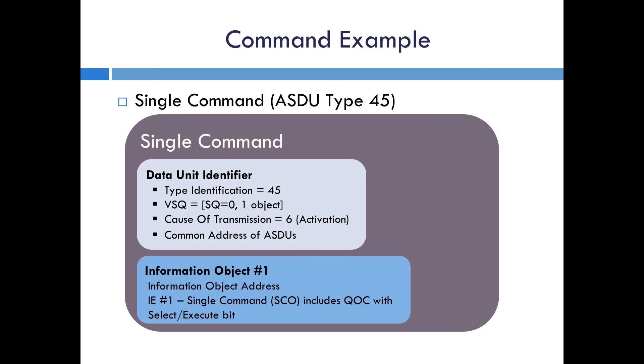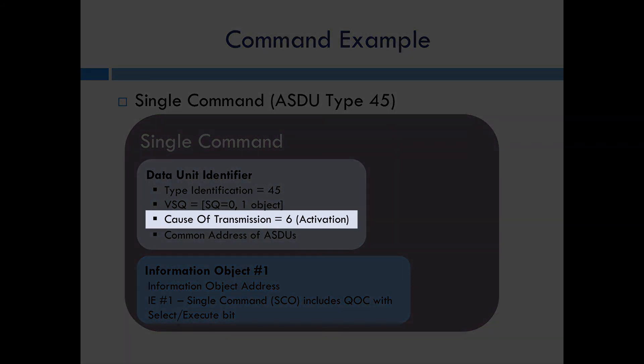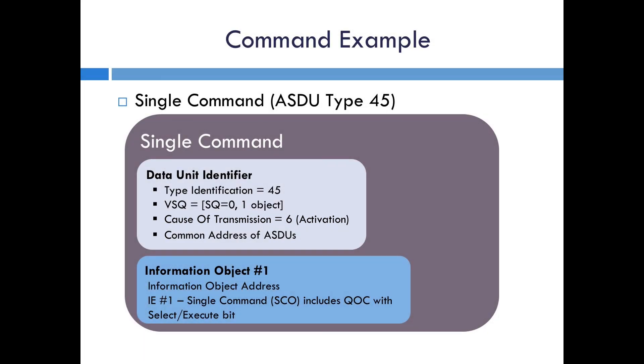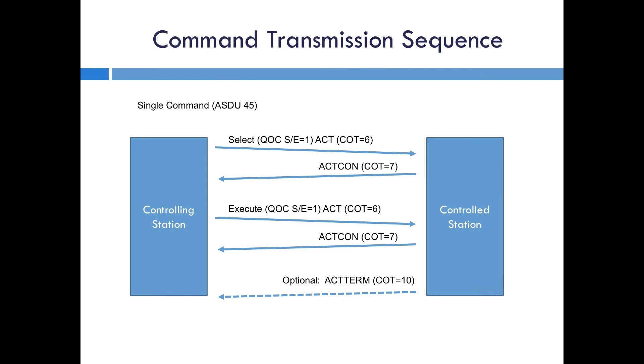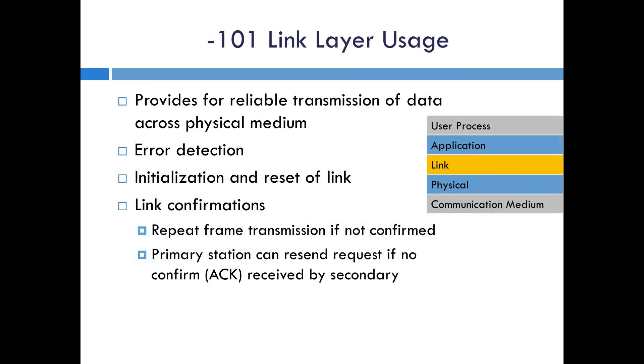Let's go back to the example of a command ASDU — the single command which is type 45. The cause of transmission when it first sends the request would be an activation, then it would get an activation confirmed back from the outstation. In the SCO you would have the bit for select or execute. In the full sequence this would first be sent with the select and a cause of transmission of activation, then the ACT-CON comes back, then the execute is sent with the ACT, then ACT-CON and ACT-TERM after the control is complete, and optionally the event can be sent to show the output status. That covers everything for the application layer — next up we'll go into the link layer, which the Triangle Microworks Source Code Library will handle most of for you.